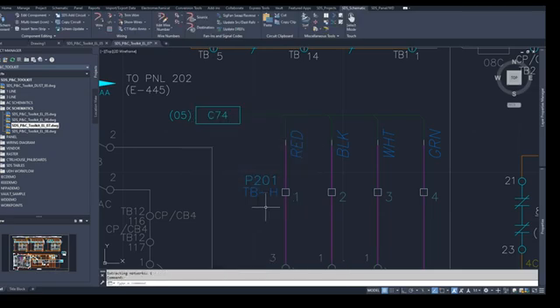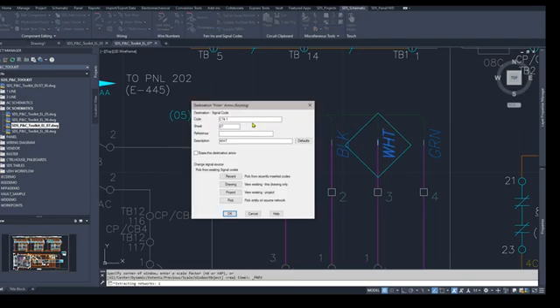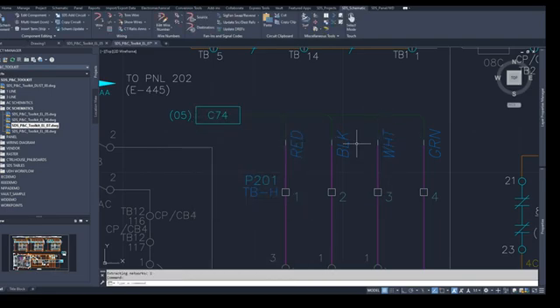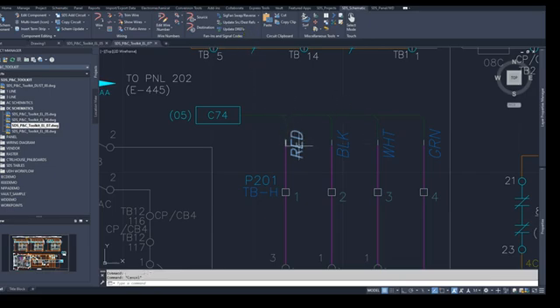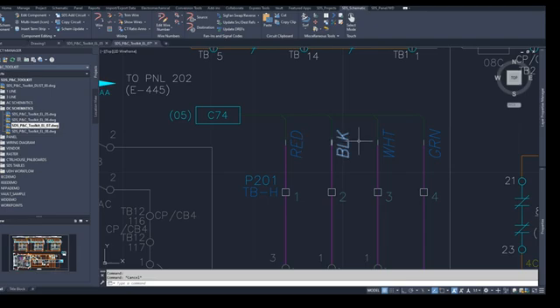And this one here is 74.1, which was the first wire. So really what the swap tool is doing is not changing the colors but it's changing the signal codes, which then of course changes the colors and where the wires connect, so you have accurate drawings in your component.